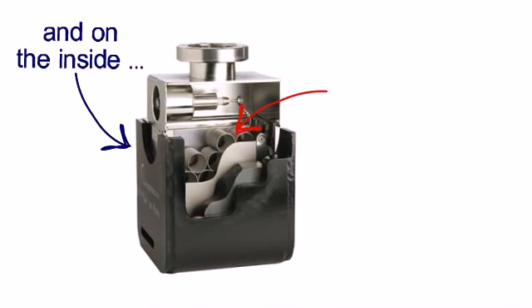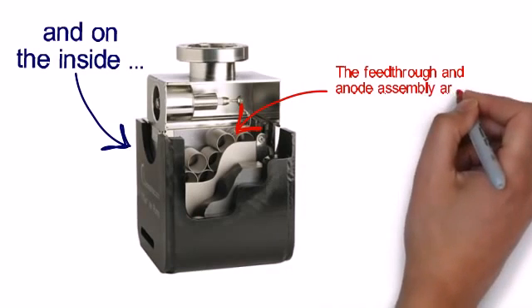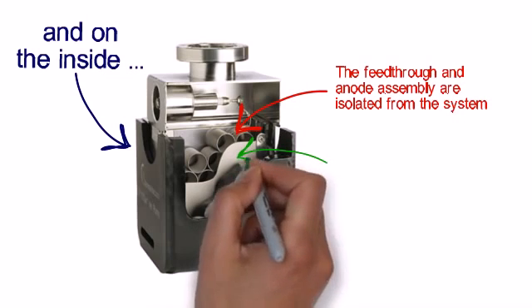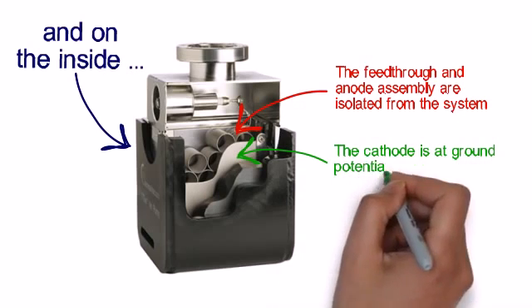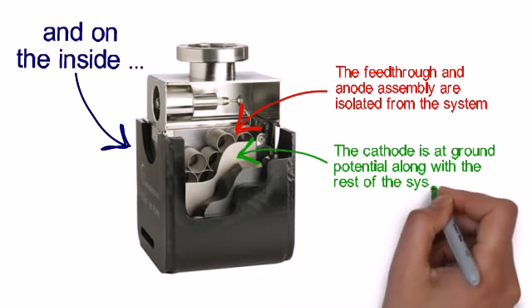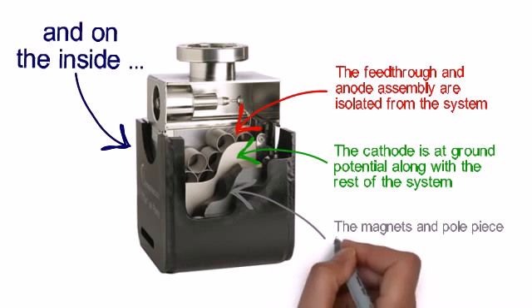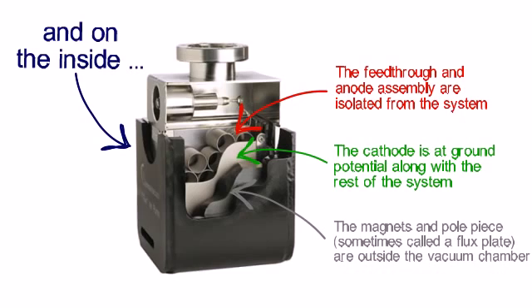We start with a feed-through and an anode assembly made out of stainless steel anode tubes. Those are isolated from the rest of the system, electrically isolated, that is. Pointing to the green there are cathodes that are at ground potential along with the rest of the system. And external to those are magnets and pole pieces, sometimes called flux plates, that are on the outside of the vacuum chamber.